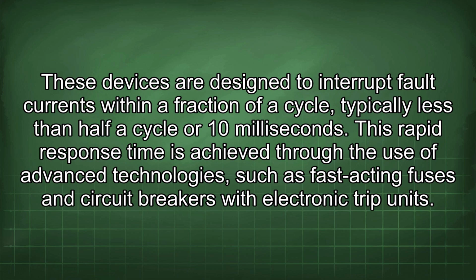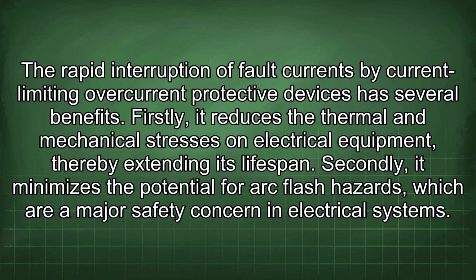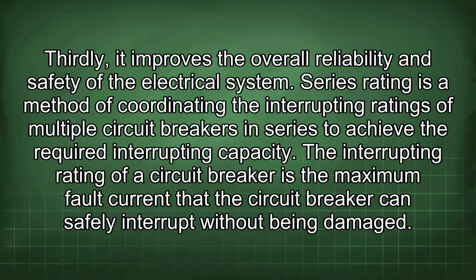This rapid response time is achieved through the use of advanced technologies, such as fast-acting fuses and circuit breakers with electronic trip units. The rapid interruption of fault currents by current-limiting overcurrent protective devices has several benefits. Firstly, it reduces the thermal and mechanical stresses on electrical equipment, thereby extending its lifespan. Secondly, it minimizes the potential for arc flash hazards, which are a major safety concern in electrical systems. Thirdly, it improves the overall reliability and safety of the electrical system.